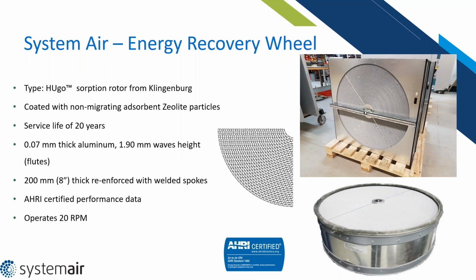So the secret sauce here is this wheel. It's a Klingenburg HUgo sorption wheel. It's obviously very thick, and it's important to note that this is the type A of the wheel. We have 4 different types: type A, B, C, and D, with D being the least effective but lowest pressure drop. So let's say you don't need the absolute most energy recovery efficiency. We can actually downgrade that a little bit to save on the static pressure. There's something worth noting there.